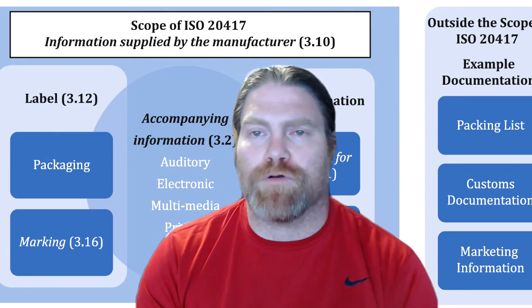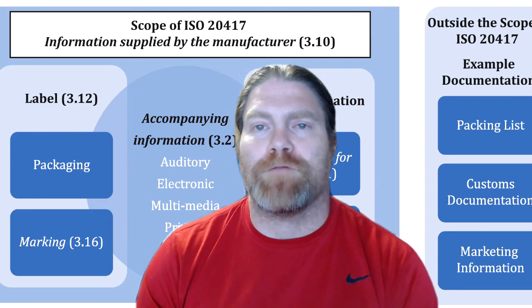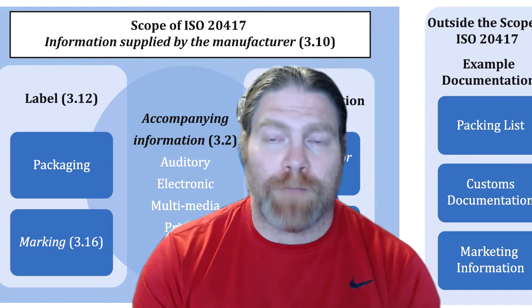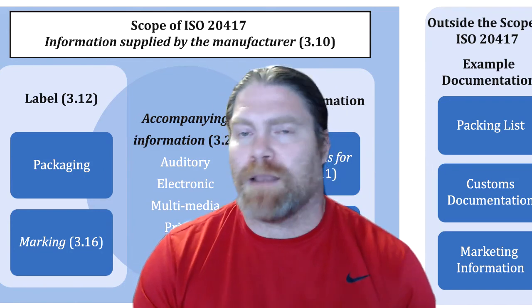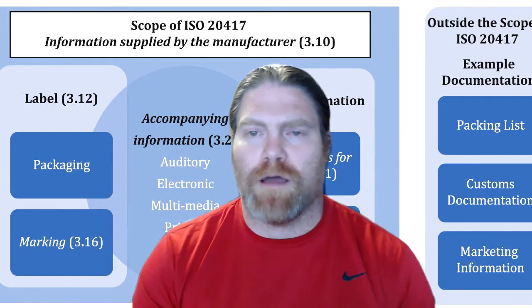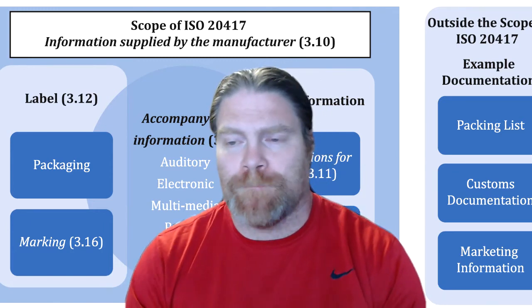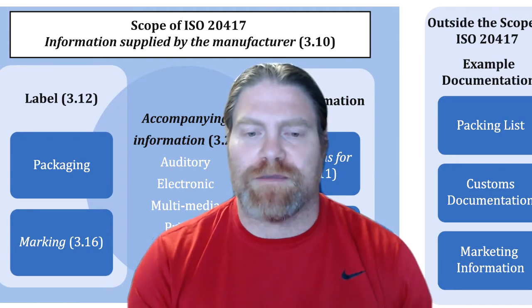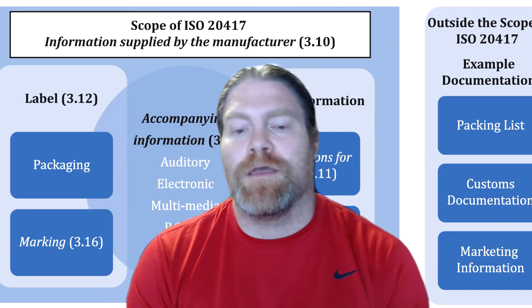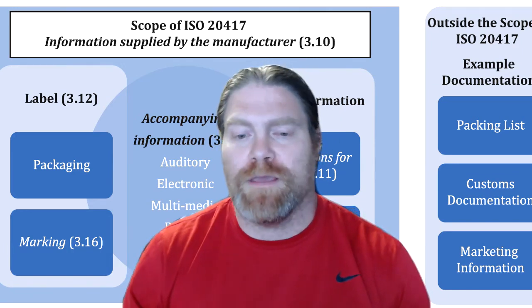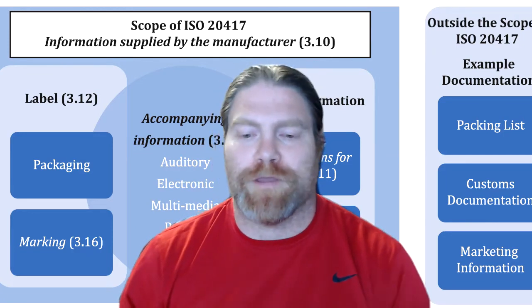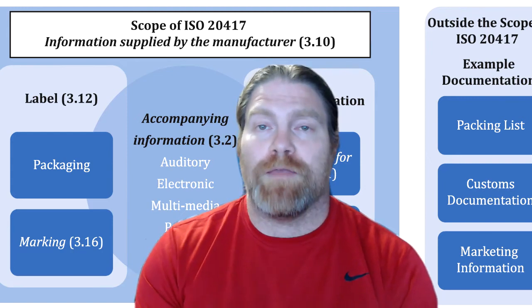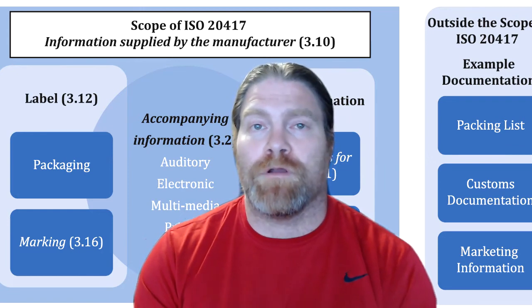Another thing that comes up is in one of the articles for economic operators — specifically the importer — there's a requirement for the importer to apply a label that includes their contact information. It could be applied by the importer or by your company on behalf of the importer. A lot of people have been arguing that it doesn't specifically say you have to apply that information on the label itself, and asking whether you could provide it on the declaration of conformity instead. However, when EN ISO 20417:2021 was released in April of this year, there is a section specifically for the importer that says the importer shall apply a label indicating their contact information. It even references a symbol for the importer: 5.1.8.